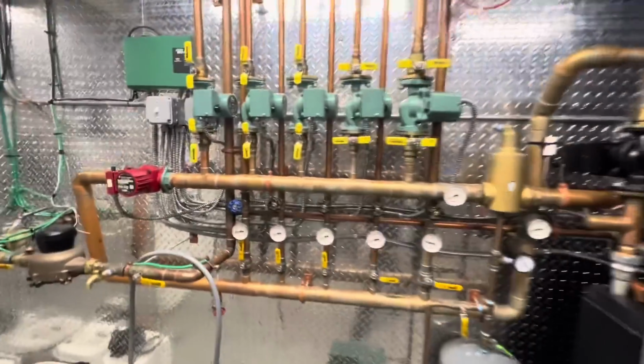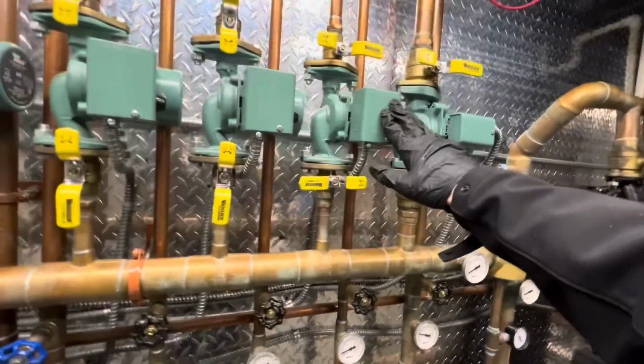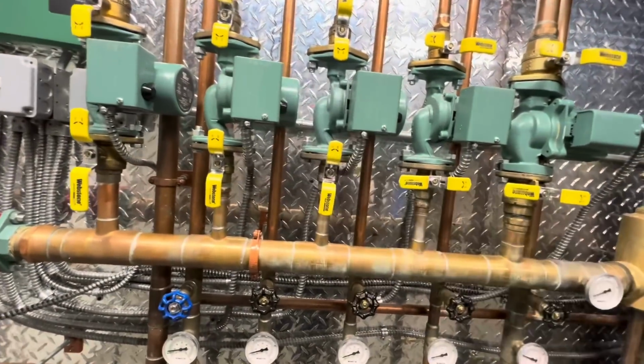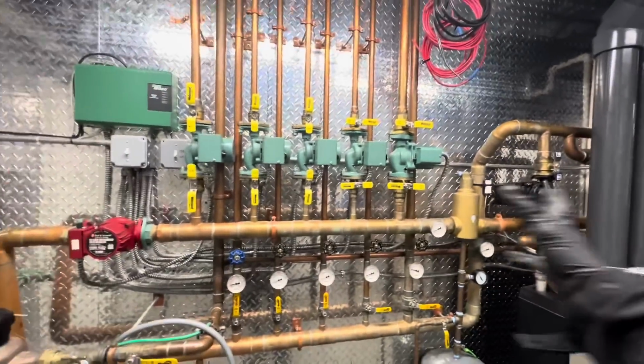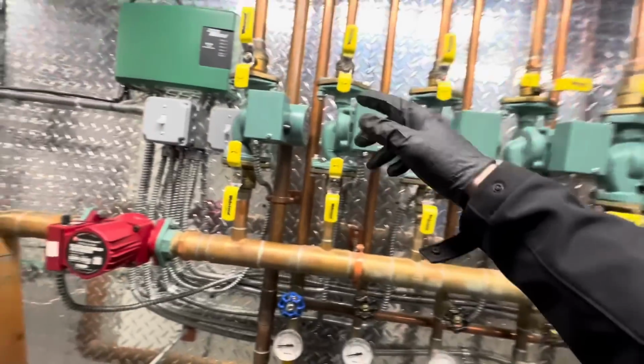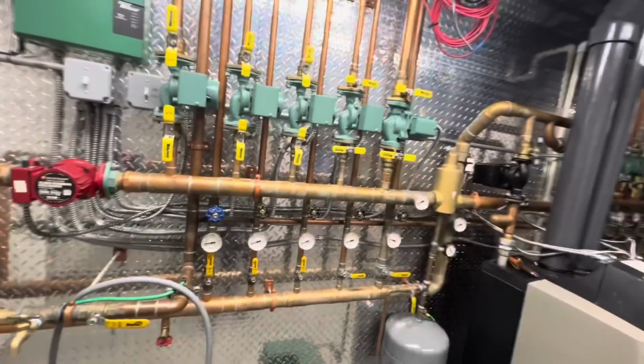And in these 3 pumps, we have check valves, which are not needed because all 3 pumps run at the same time, it's a snow melt system. So we're going to take those check valves out because he's noticed that it restricts his flow.